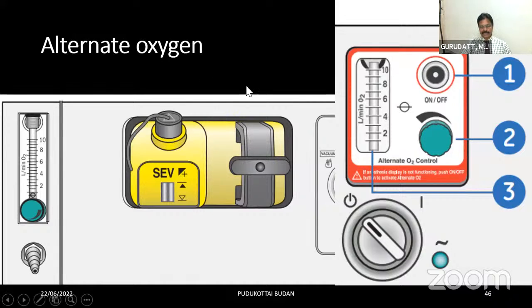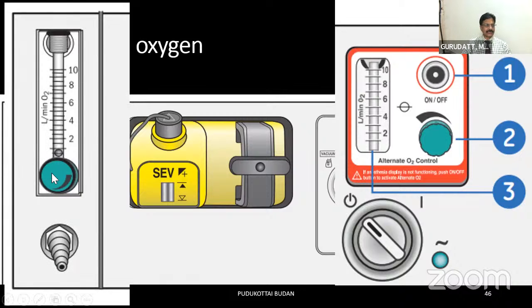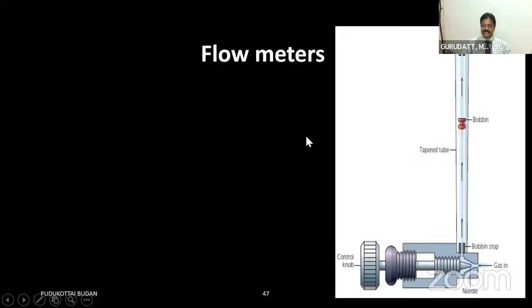In modern workstations we have the electronic hypoxic guard because flow sensors are there, and they always accurately provide oxygen of more than 25%. In the Aisys CS2 machine we also have the auxiliary source of oxygen, an extra source. Even if the whole electronic system is not functioning, you can still connect your open circuit to this auxiliary source of oxygen and ventilate the patient without producing any hypoxia. That is an additional safety feature adopted in modern workstations.